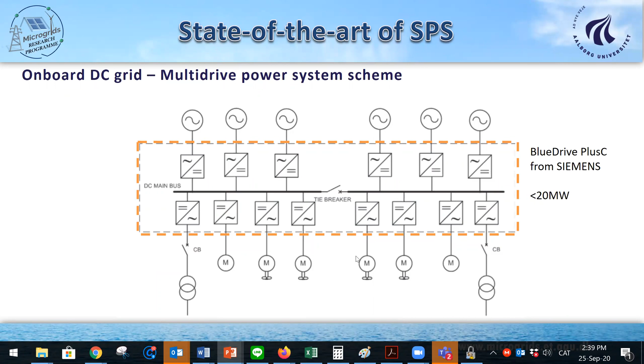If you take a look, for instance, at a DC microgrid for a ship, you have a number of diesel generators, and then we can have a number of rectifiers, so AC to DC converters, and then we have 2 buses. This is for redundancy, because if a short circuit or overload happens, we can open this breaker and the other bus will still work. Then we have a number of propellers, basically motors, supplied by inverters with variable frequency, and inverters with fixed frequency for supporting the AC loads in the ship. All these motors are with variable frequency because you have to change according to the mission of the ship, how the speed will be.